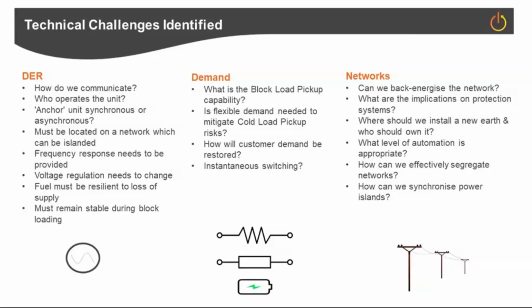Third set of challenges around the networks. Certainly the GB power system is not designed to be back energized. So back energizing from the 33 kV distribution system up to the 132 kV and up to the 275 and 400 kV supergrid systems, it's not necessarily designed to do that. It's designed to be top down rather than bottom up. So what are the challenges around that?